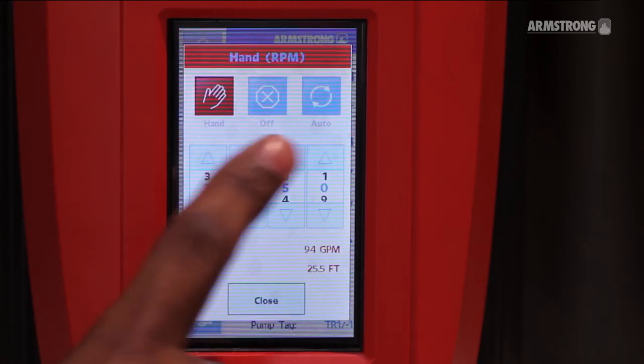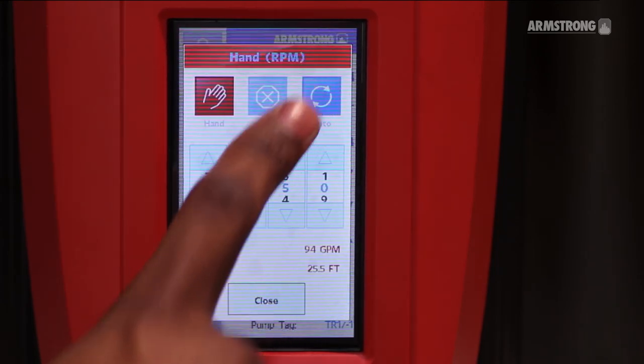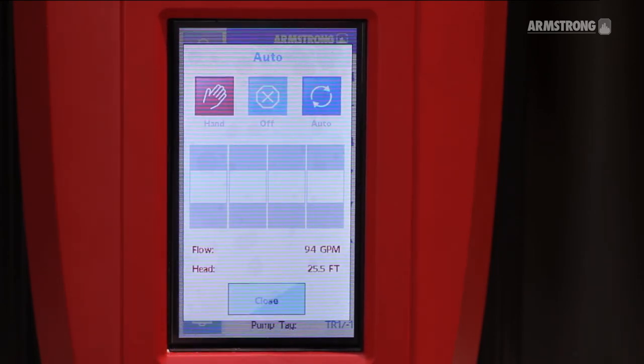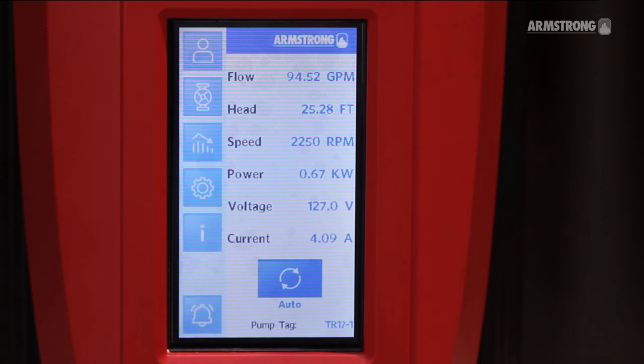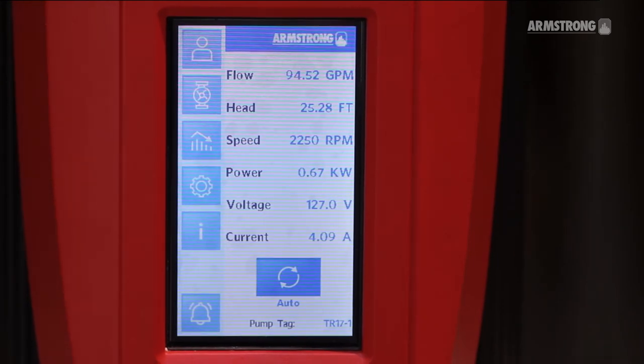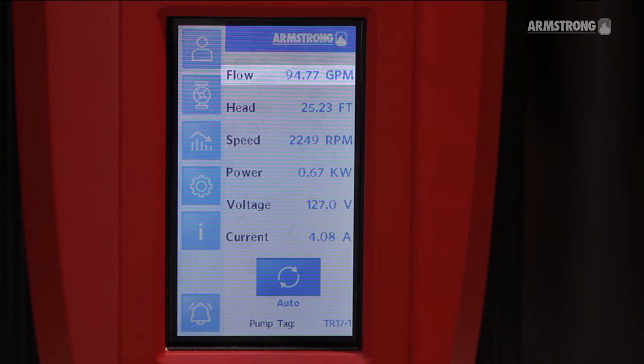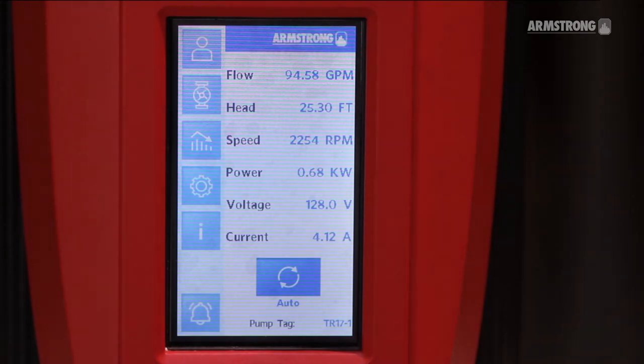With all valves fully open, the pump should ramp to find the desired flow. By throttling the discharge valve, the pump will try to maintain the same flow rating whenever possible. The pump is now configured to work in Constant Flow Control.